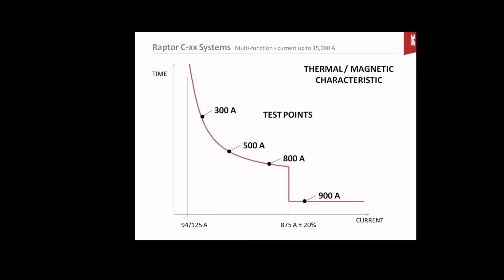This is a simple graphic representation of these characteristics. And I am showing here the collection of points that we are going to test. This is just a collection of current values. We are going to test the circuit breaker under 300 ampere, 500 ampere, 800 ampere, and 900 ampere. If you wish, we can add more test points. No problem. I will show you how much current we are able to inject in the conditions that we have here in this office right now.